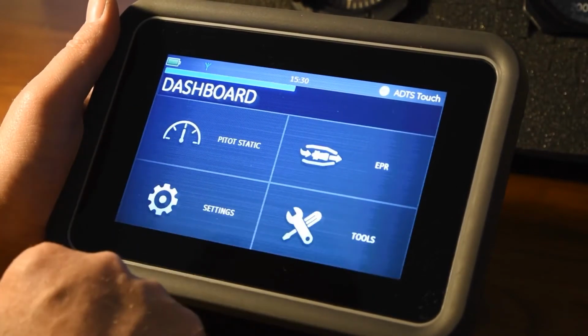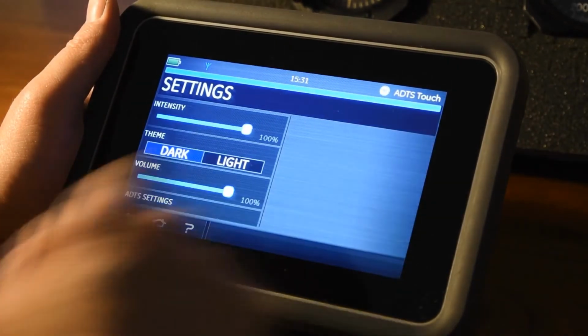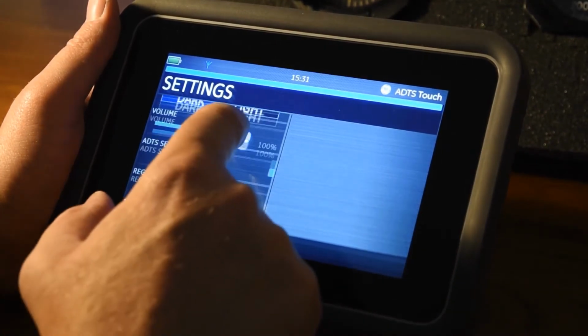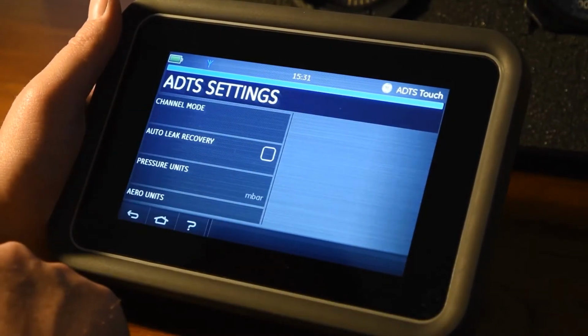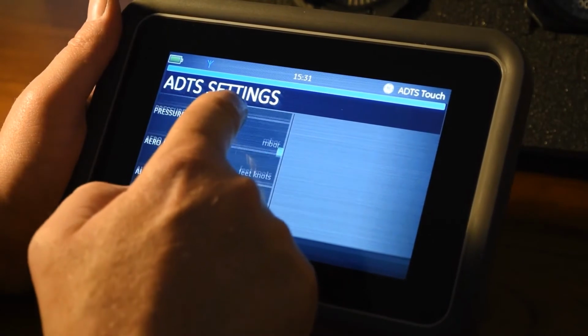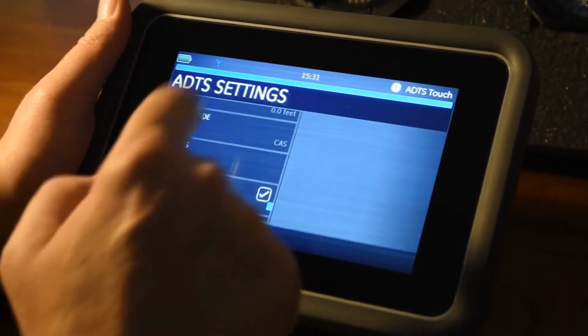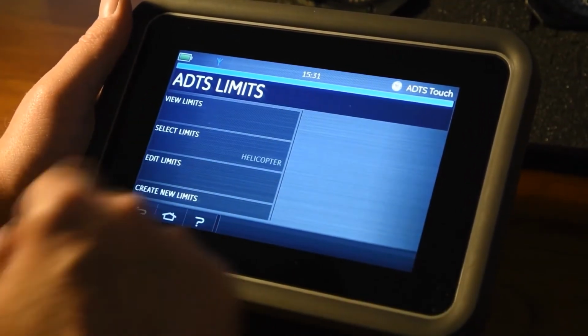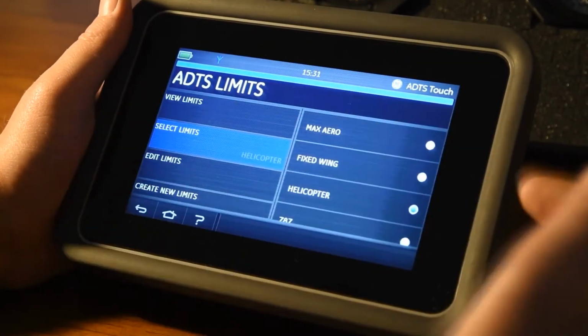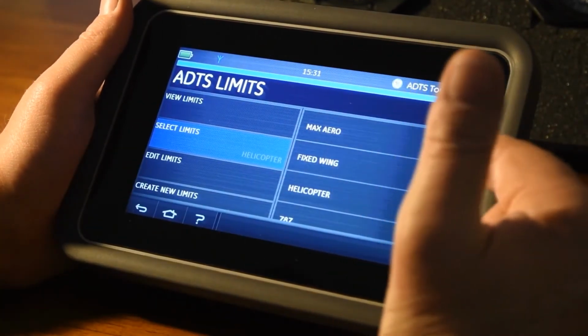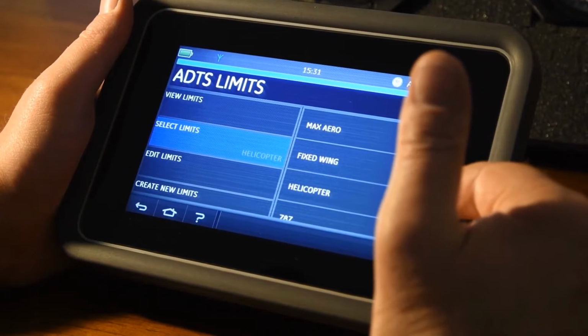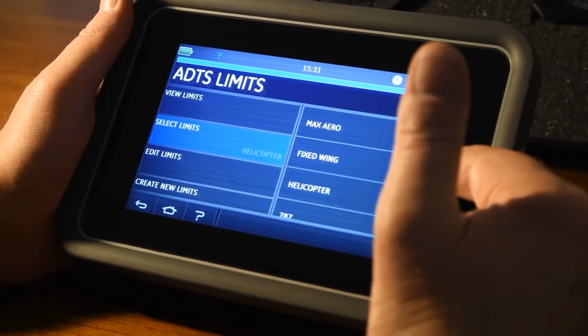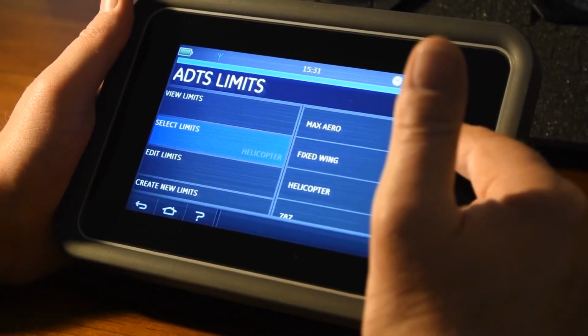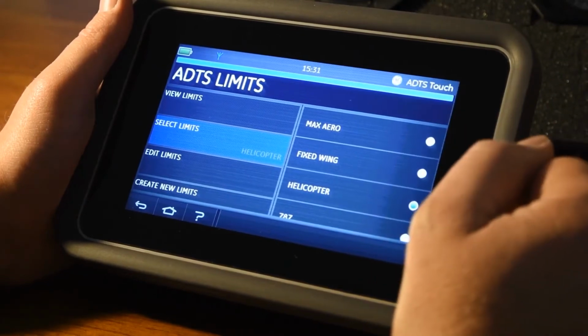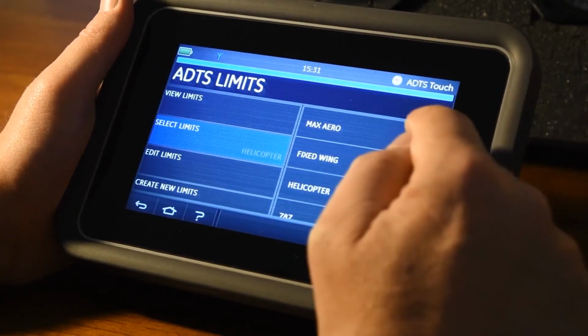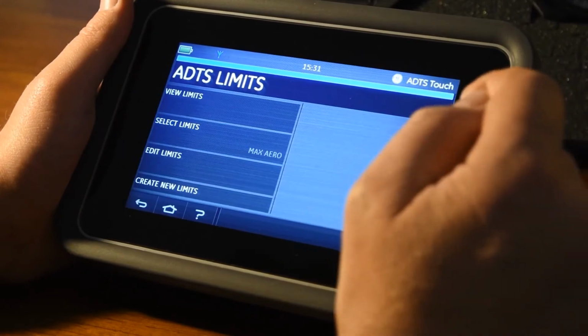So if we go back to the home screen and go to settings, and scroll down here to look at ADTS settings, I just go into ADTS limits. Now I want to select limits - at the moment, as I said, it was on helicopter. We've got typical fixed wing, or we've got max. So max aero is the maximum capability of the instrument. For the sake of the test, that's the one I'll select.